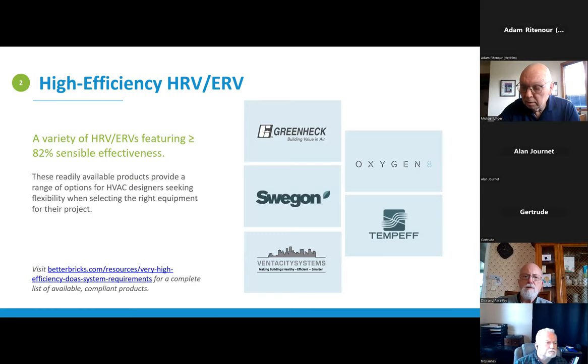Okay, so we have that second component, the high efficiency HRV ERV. So there are a variety of HRVs and ERVs that boast that greater than or equal to 82% sensible effectiveness. You see 5 of those manufacturers here on the screen, and you can see a whole list of those compliant products at betterbricks.com. But what are those minimum requirements for high efficiency HRV or ERVs?